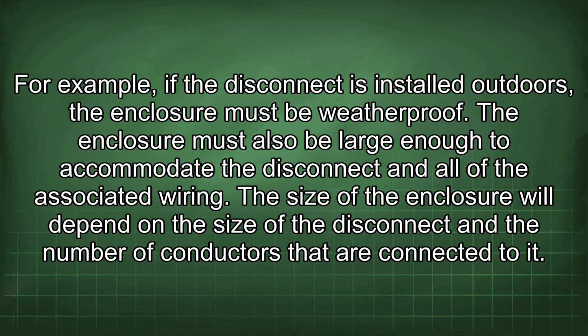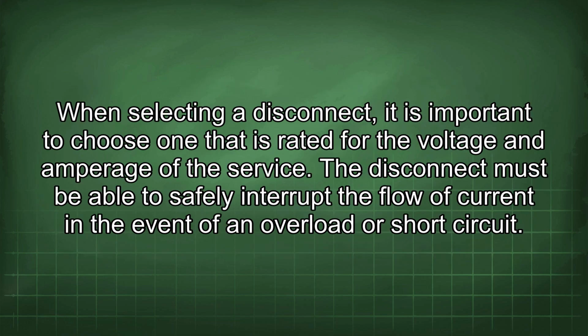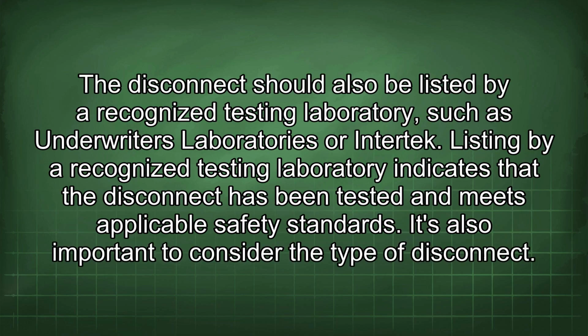connected to it. When selecting a disconnect, it is important to choose one that is rated for the voltage and amperage of the service. The disconnect must be able to safely interrupt the flow of current in the event of an overload or short circuit. The disconnect should also be listed by a recognized testing laboratory such as Underwriters Laboratories or Intertek. Listing by a recognized testing laboratory indicates that the disconnect has been tested and meets applicable safety standards.